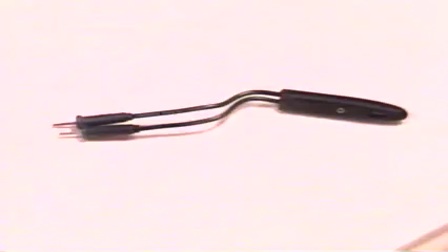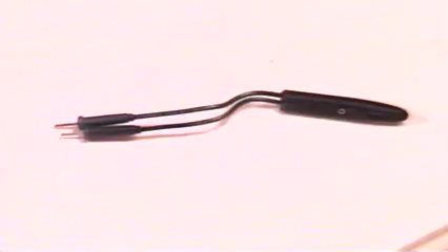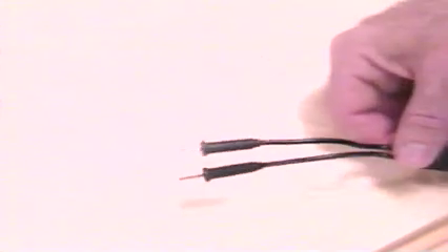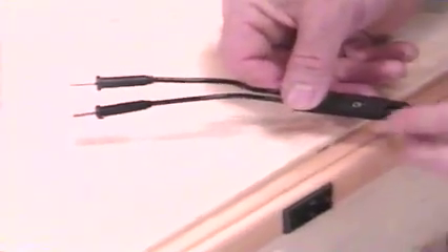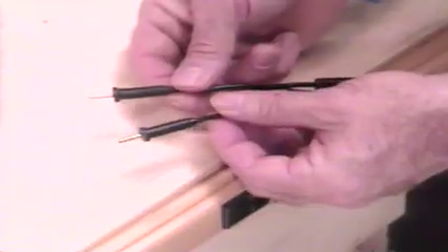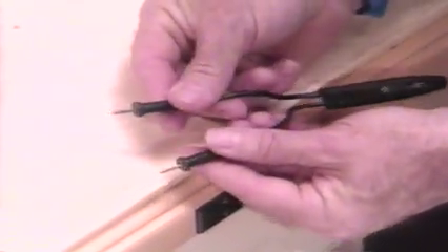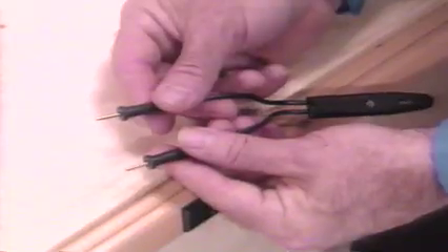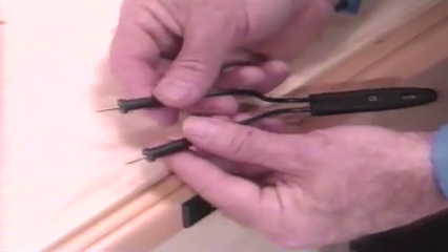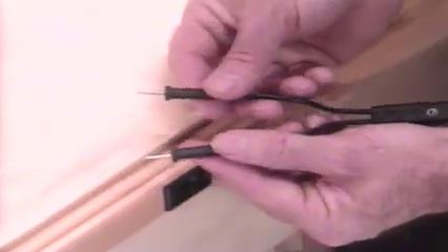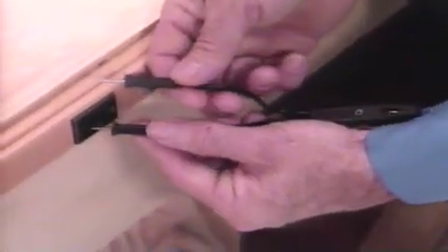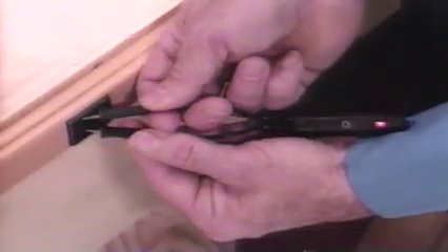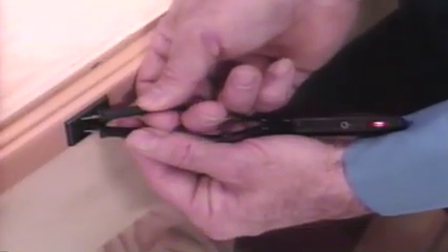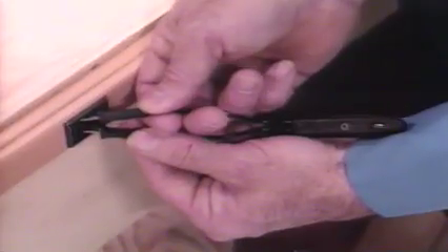A neon circuit tester is used to determine if voltage is present in a circuit and if the circuit is properly grounded. Basically, it is a small neon glow lamp with a pair of wire leads. By holding the insulated ends of the leads and touching the protruding metal contact tips on the hot and neutral wires, the light will glow if voltage is present. For example, to check an outlet for voltage and proper ground, first insert the tester leads into the hot and neutral slots of the outlet. If the circuit is hot, the light will glow.